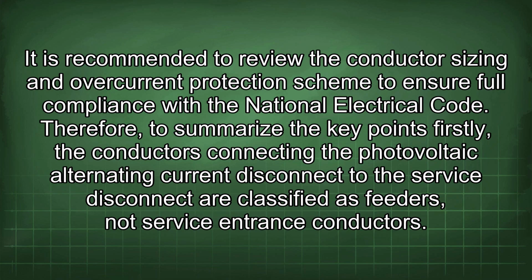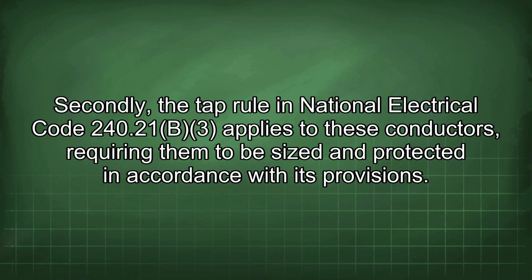the National Electrical Code. Therefore, to summarize the key points, firstly, the conductors connecting the photovoltaic alternating current disconnect to the service disconnect are classified as feeders, not service entrance conductors. Secondly, the tap rule in National Electrical Code 240.21(B)(3) applies to these conductors, requiring them to be sized and protected in accordance with its provisions.